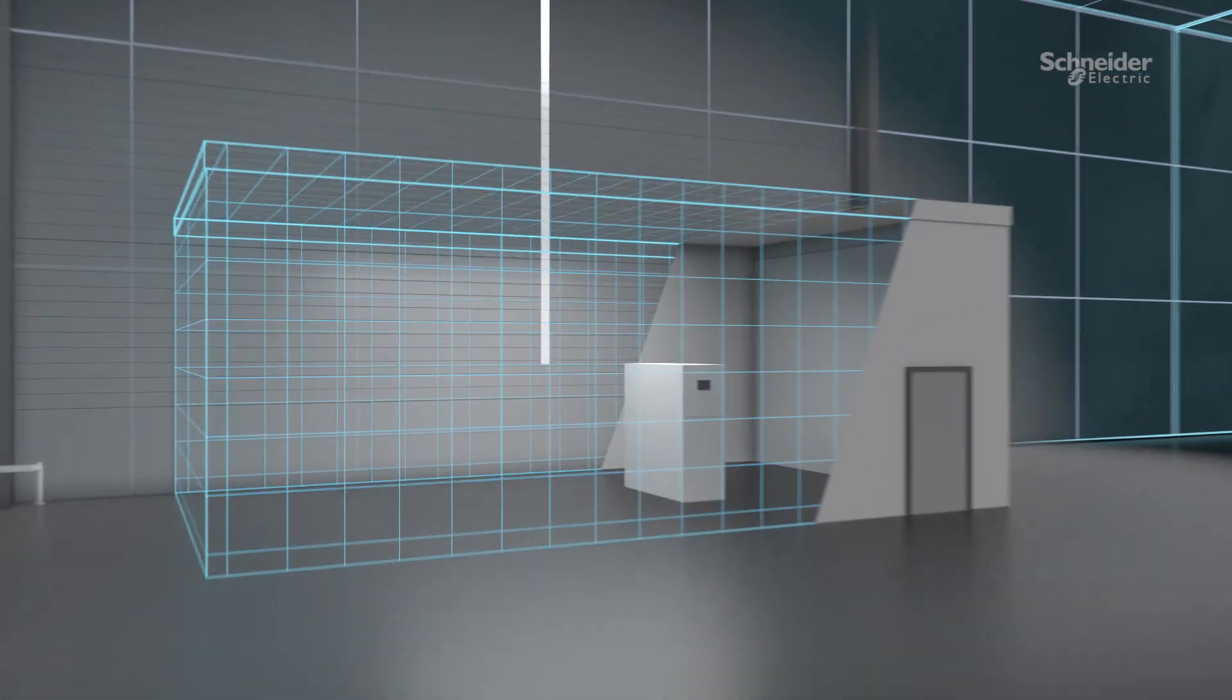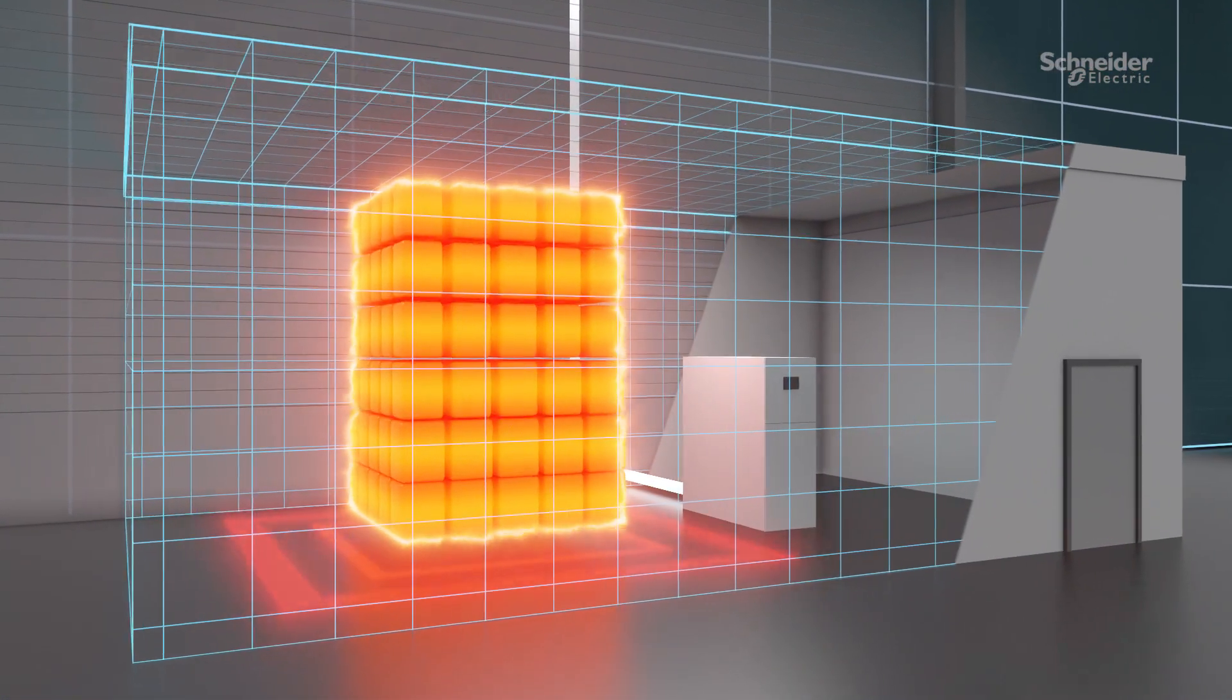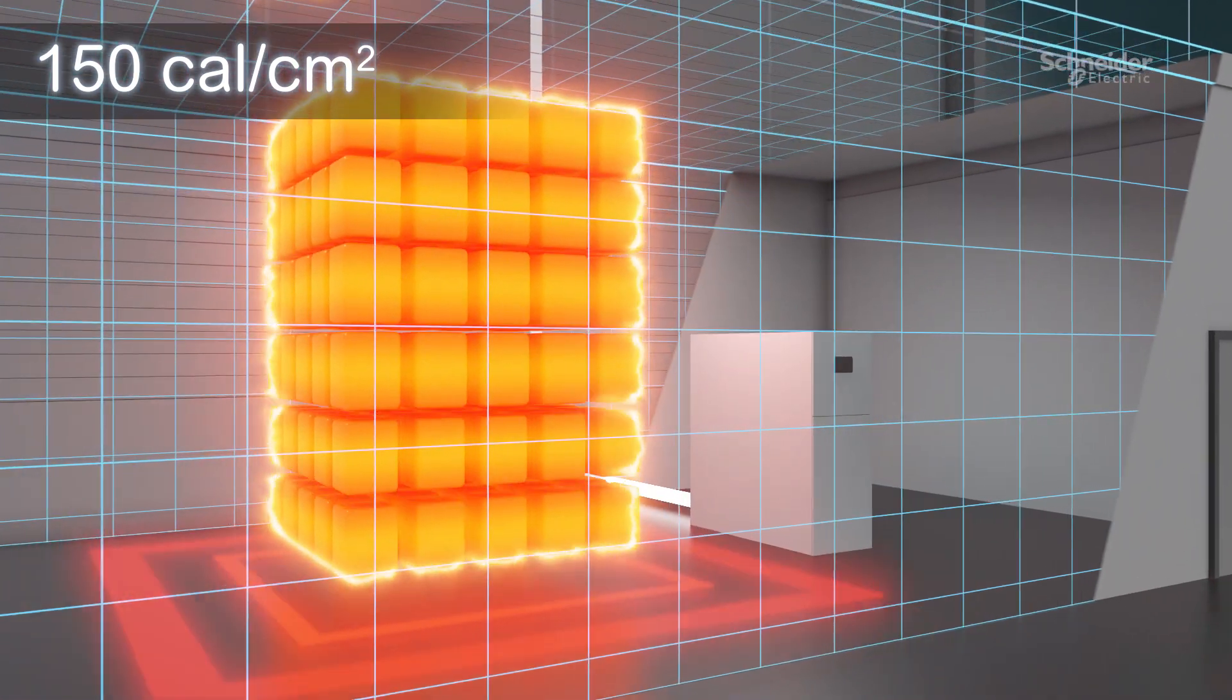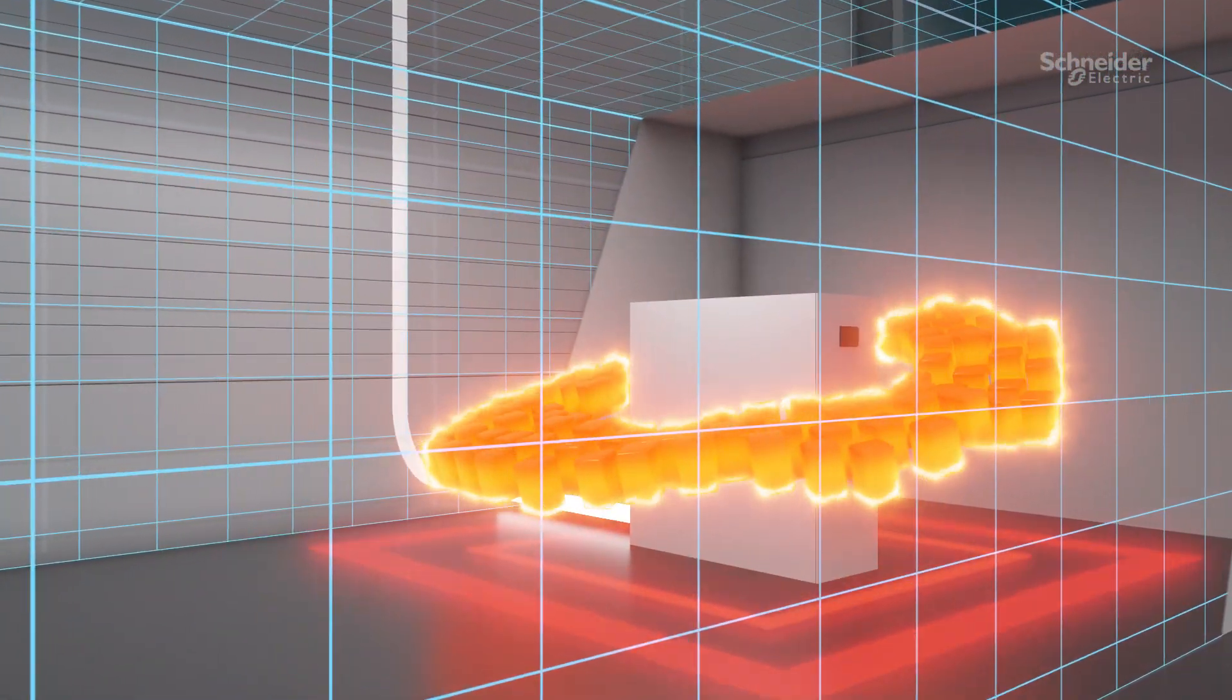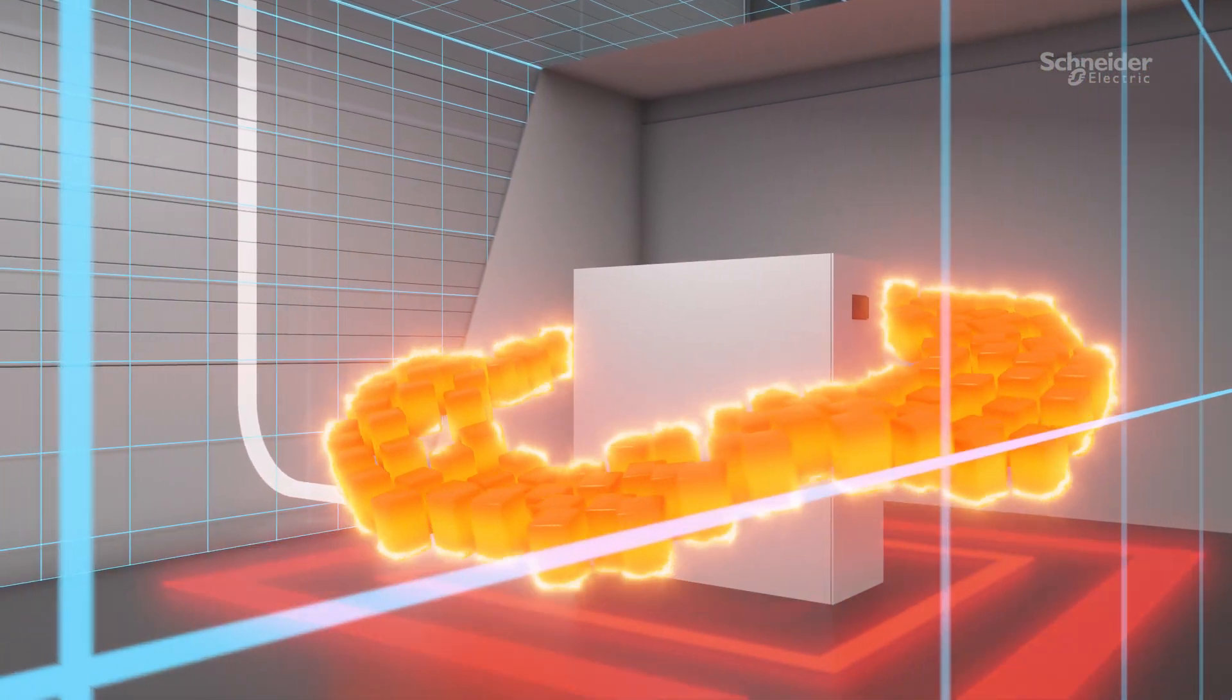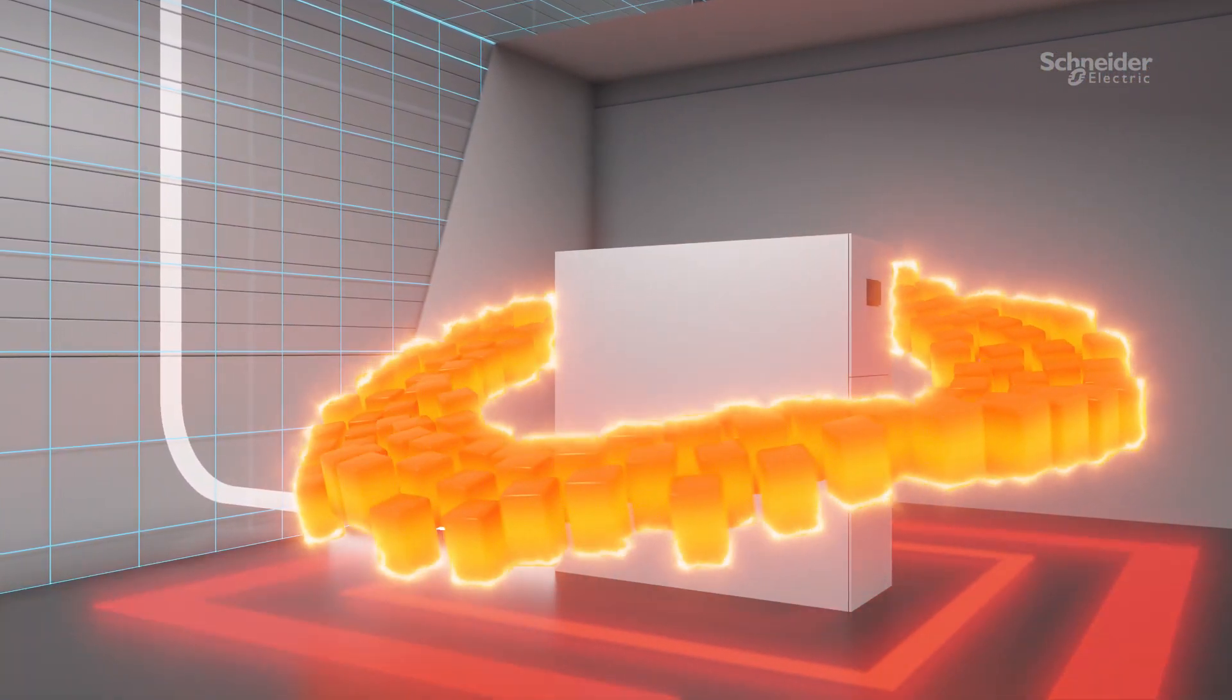Potential arc energy on an incoming main section can exceed 150 calories per square centimeter, well beyond Category 4 PPE protection. 70% of industrial facilities are fed from the utility, leaving minimal protection on the line side.